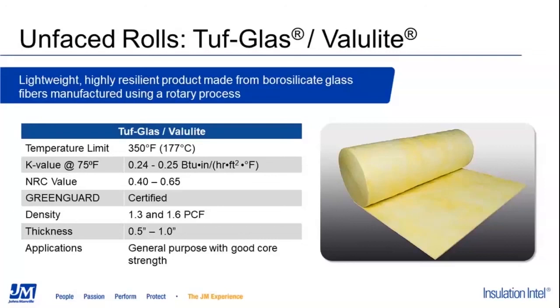The K values, the thermal values, are between 24 and 25. The NRC between 40 and 65. It is GreenGuard certified and available in densities of 1.3 or 1.6 pound density and thicknesses between 1/2 and 1 inch. Tuf-Glas Valulite does have the high post-consumer recycled content of 56%.